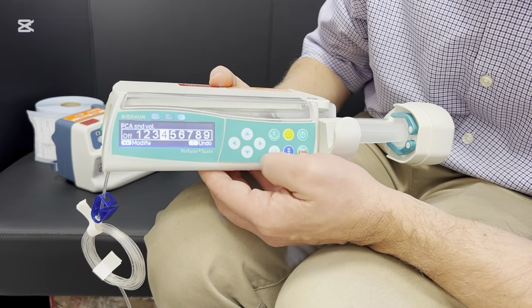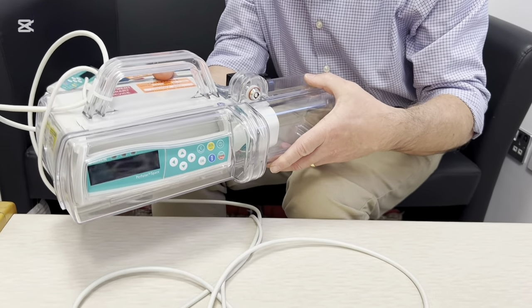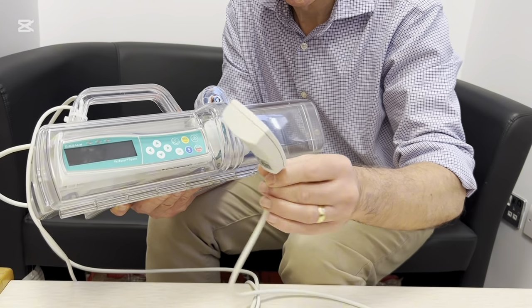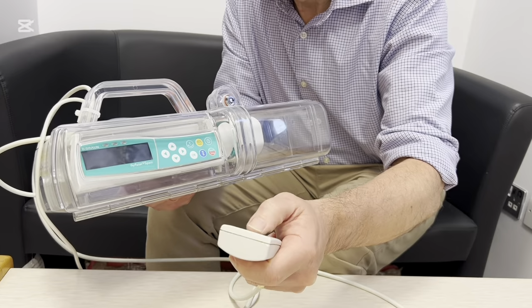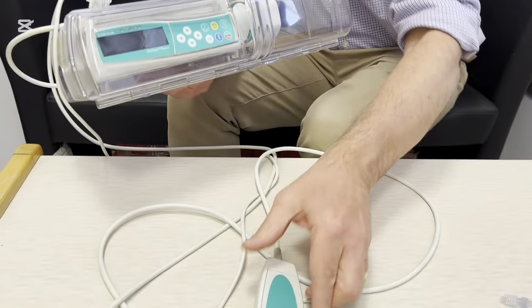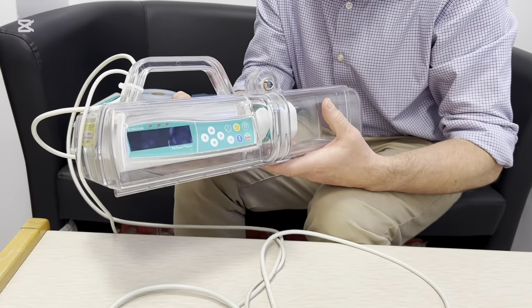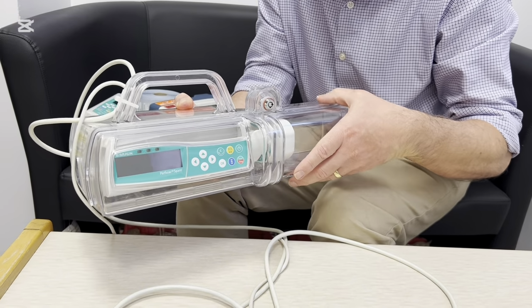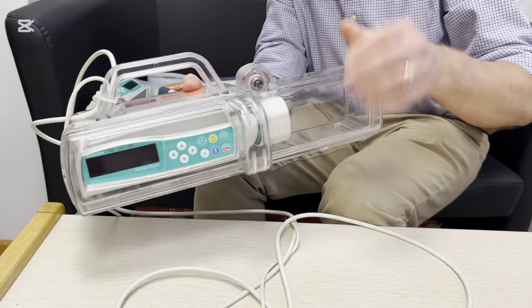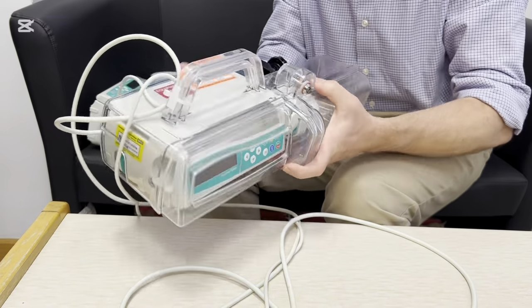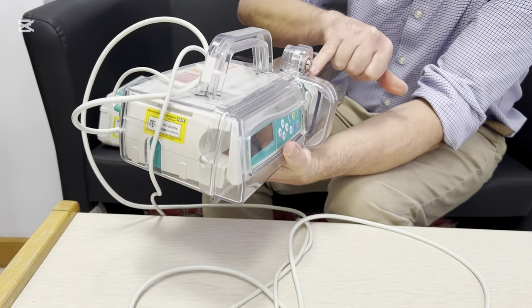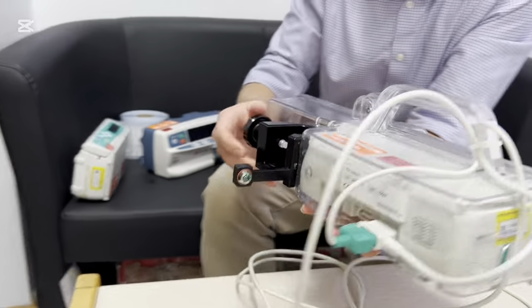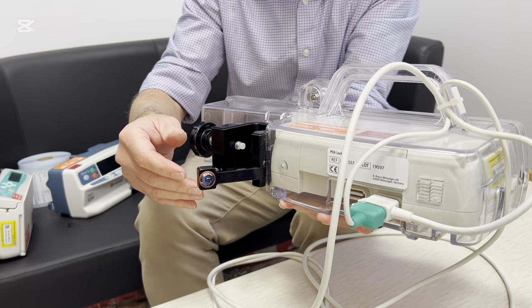Ordinarily, PCA pumps will come in a lockbox like this, and the patient gets a controller. They just press the button to receive their bolus, the pump proceeds to give the bolus to the patient, and then locks out for the prescribed 5 minutes. The lockbox is locked with a key here. There's also a lock on the back here, so that you can lock these to the pole clamp so they can't be removed.